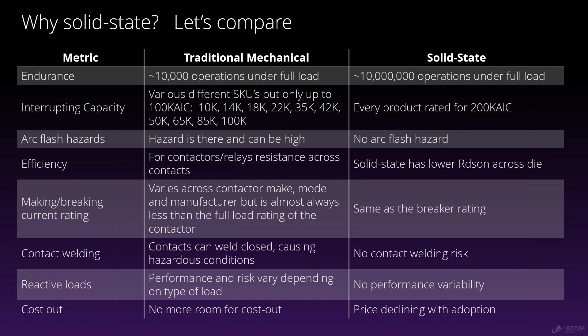So here is our 100 amp, 480 volt, 3-phase circuit breaker. Again, fastest circuit breaker in the world, fully digital controlled on and off, 200,000 amps of interrupting rating. It's got integrated metering right in the breaker for voltage, current, power factor. It's UL listed to 489, and it's programmable. So even though it's a 100 amp frame, you can program it anywhere from 15 to 100 amps with a fully customizable time current curve.